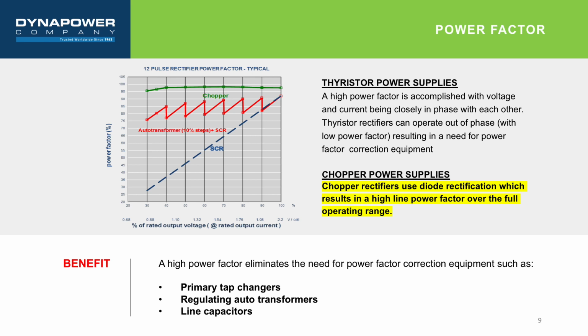But tap changers may have many steps and have a limited number of operations before requiring maintenance. In a chopper supply, however, diode rectification has no retarded firing and has constant high line power factor over a full operating range without the use of PF compensation.